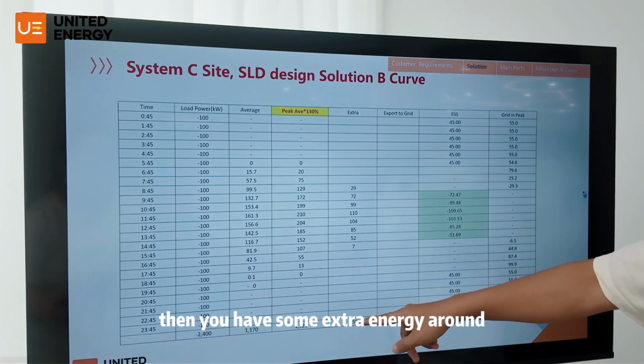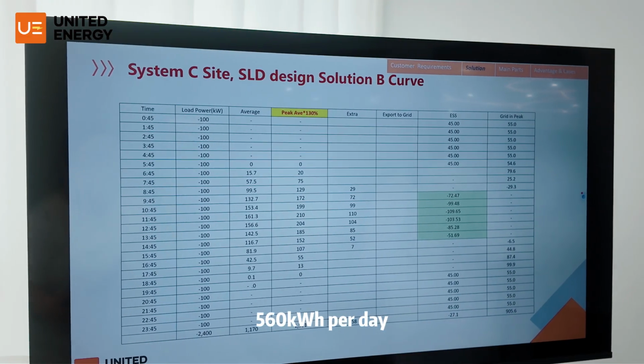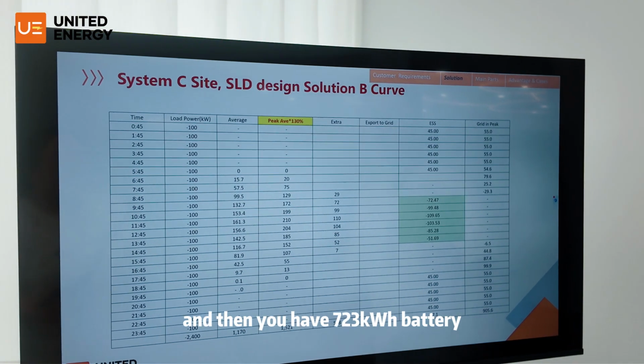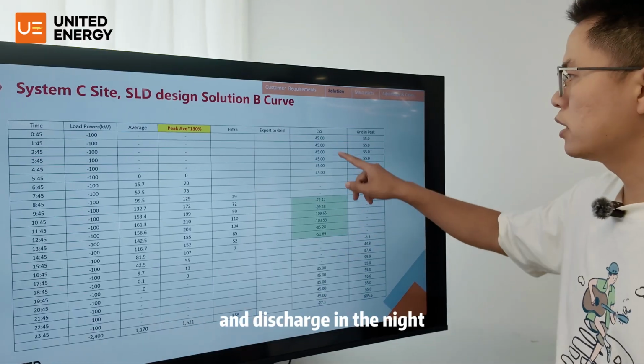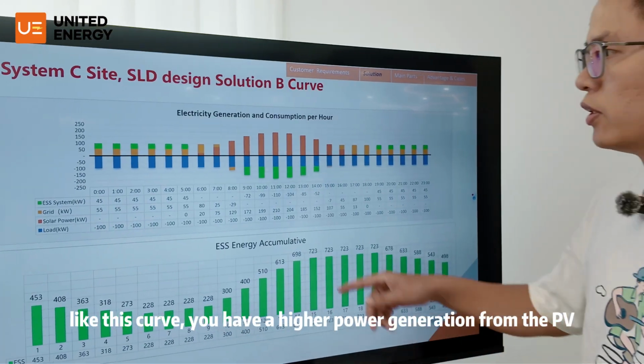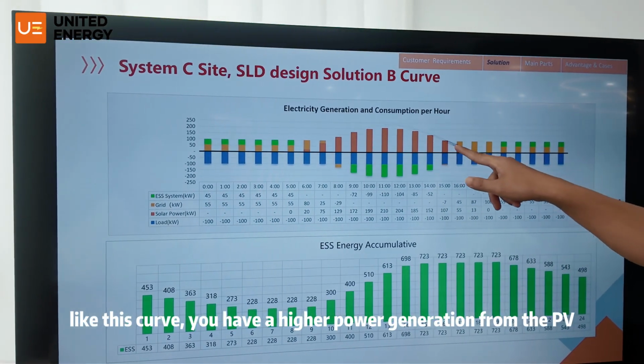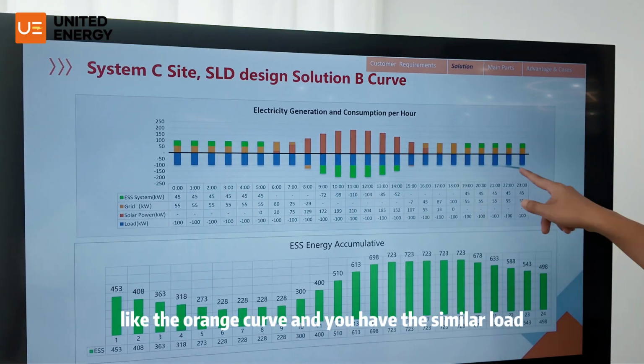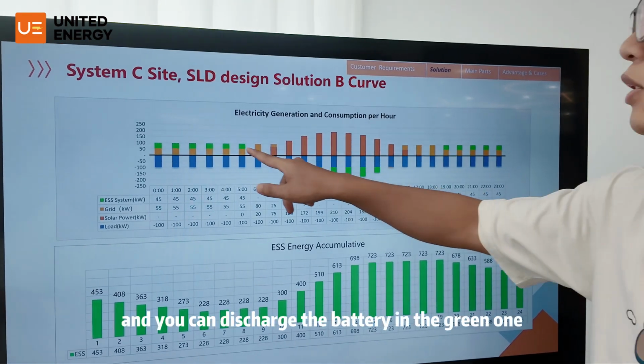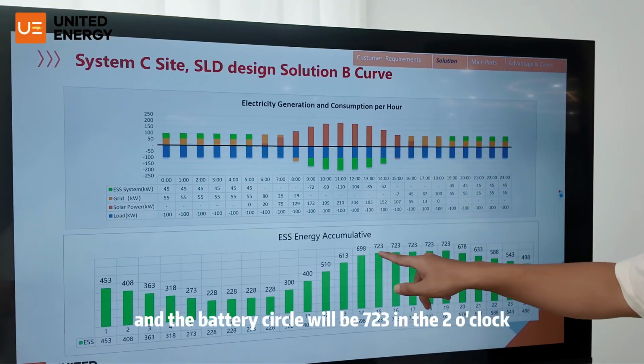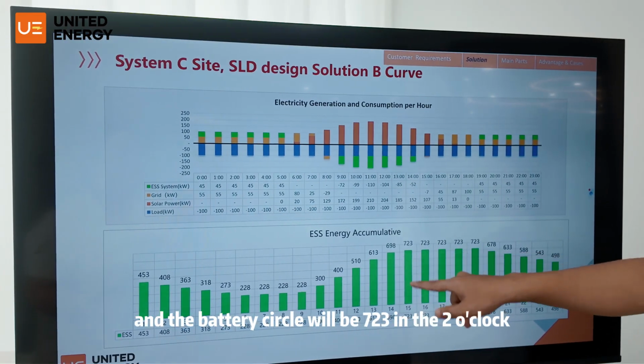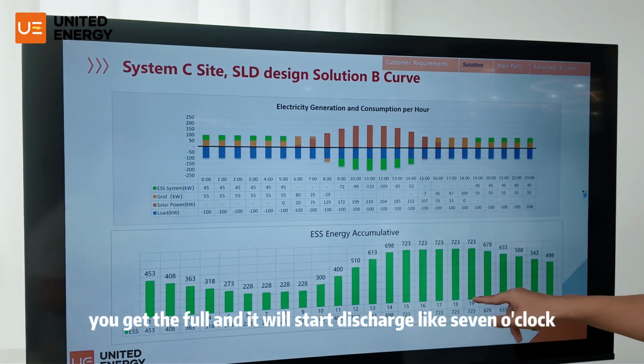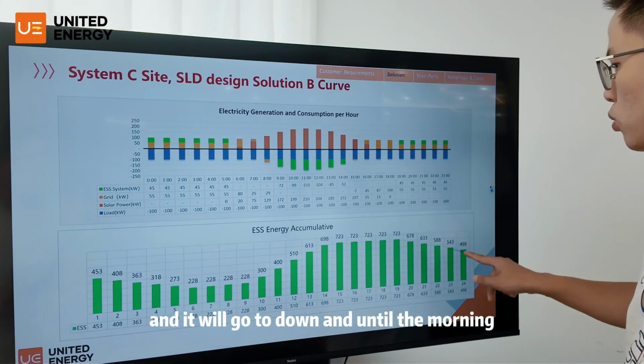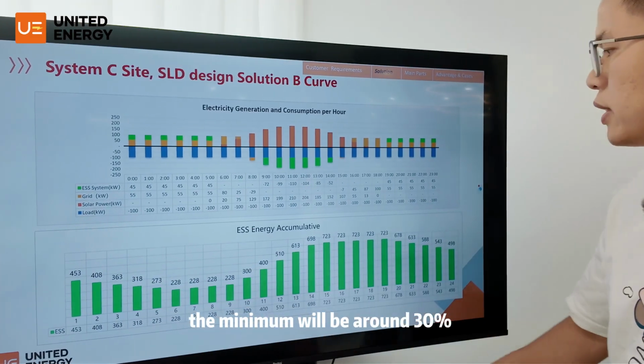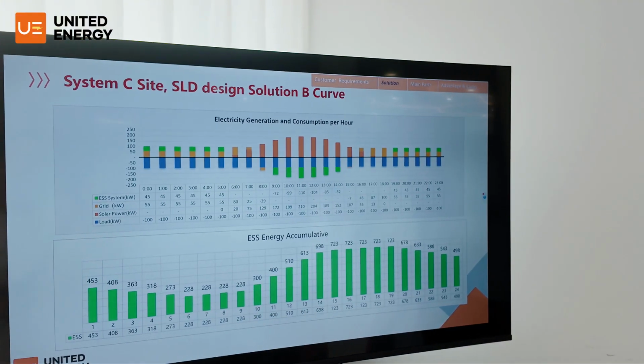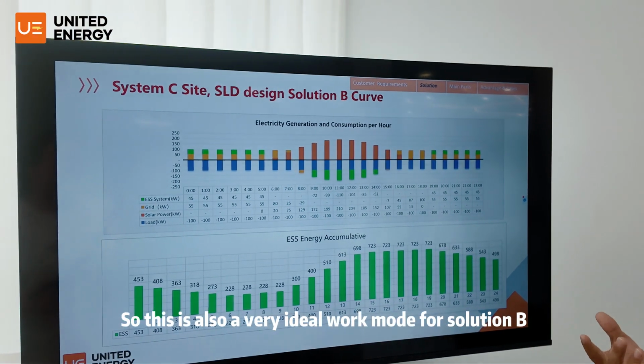Then you have some extra energy around 560 kilowatt hour per day, and then you have a 723 kilowatt hour battery. You can store that energy in the daytime and discharge in the night. Like this curve, you have a higher power generation from the PV, the orange curve, and you have a similar load, and you have the extra energy, the green one, to charge the battery, and you can discharge the battery in the green one. And the battery capacity will be 723. At 2 o'clock or 3 o'clock you get full, and it will start discharging around 7 o'clock and go down, until the morning the minimum will be around 30%. This is also a good curve. So this is also a very ideal work mode for solution B.